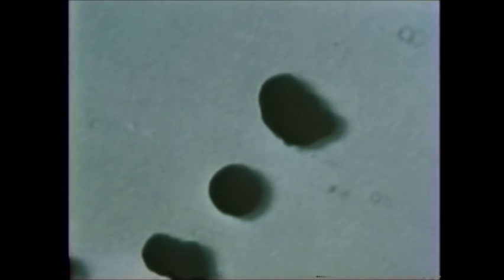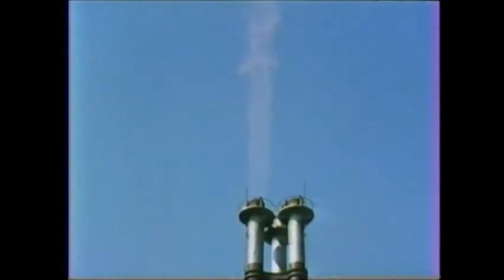Since the gas is treated in the unburnt state, the dust particles are coarser and much easier to collect than in other processes. At the outlet of the venturi, the gas is as clean as less than 0.05 grams of dust per normal cubic meter or 0.02 grains per standard cubic foot.